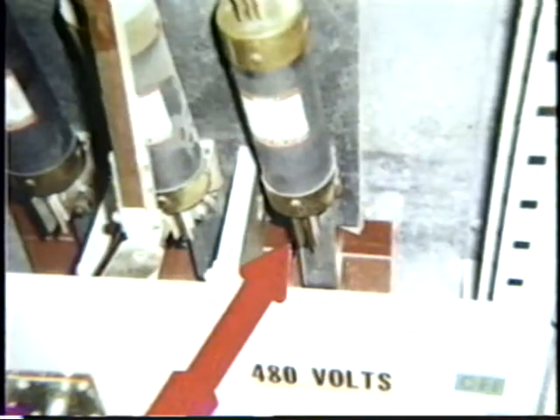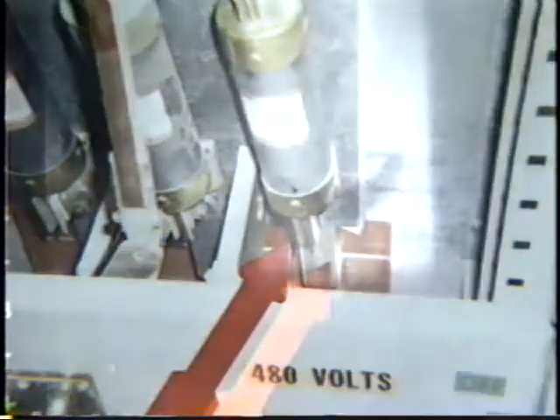In this photograph, we see a 400 amp fuse located in a motor control center. The system is operating normally, and there is no reason to suspect a growing problem until we see the fuse under infrared photography. A temperature rise of 9 degrees Celsius is found, and the pattern of the heat suggests that a poor connection exists between the fuse and the load side fuse clip.